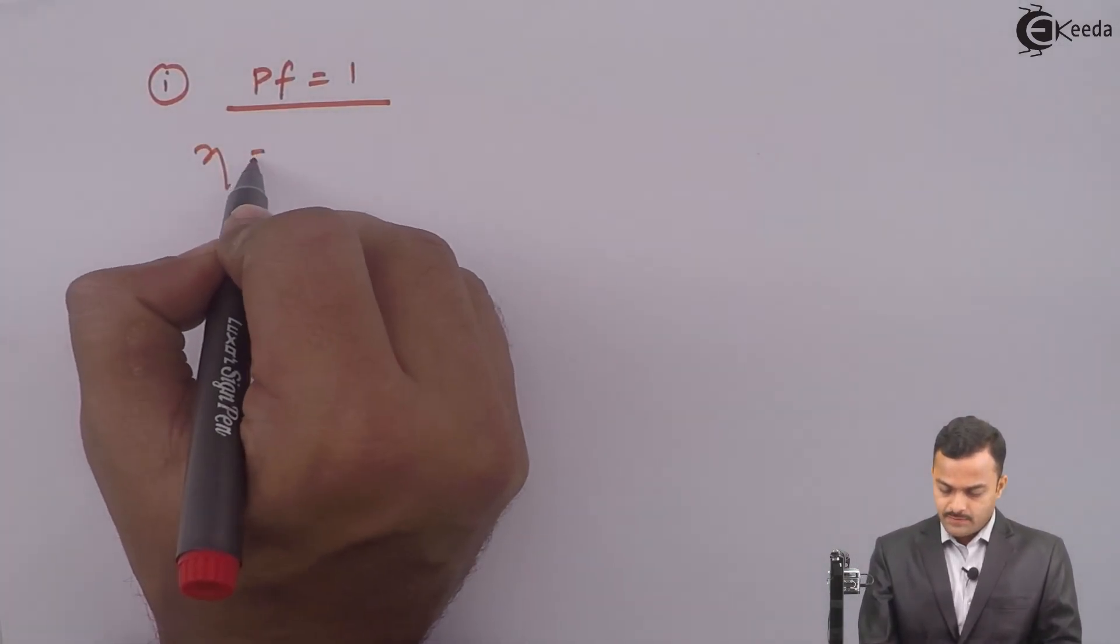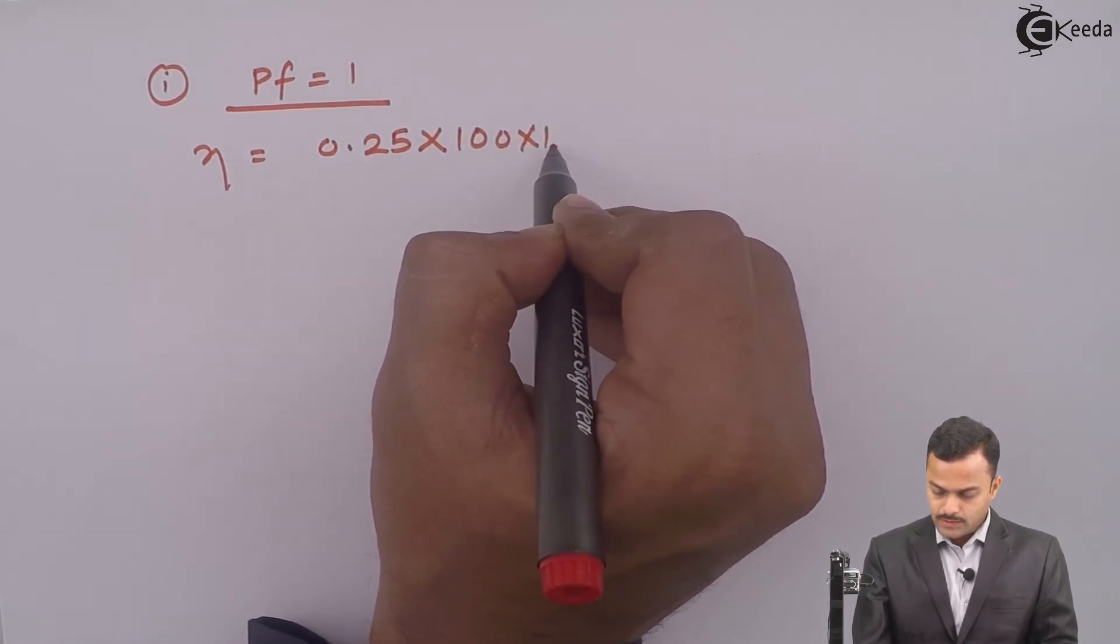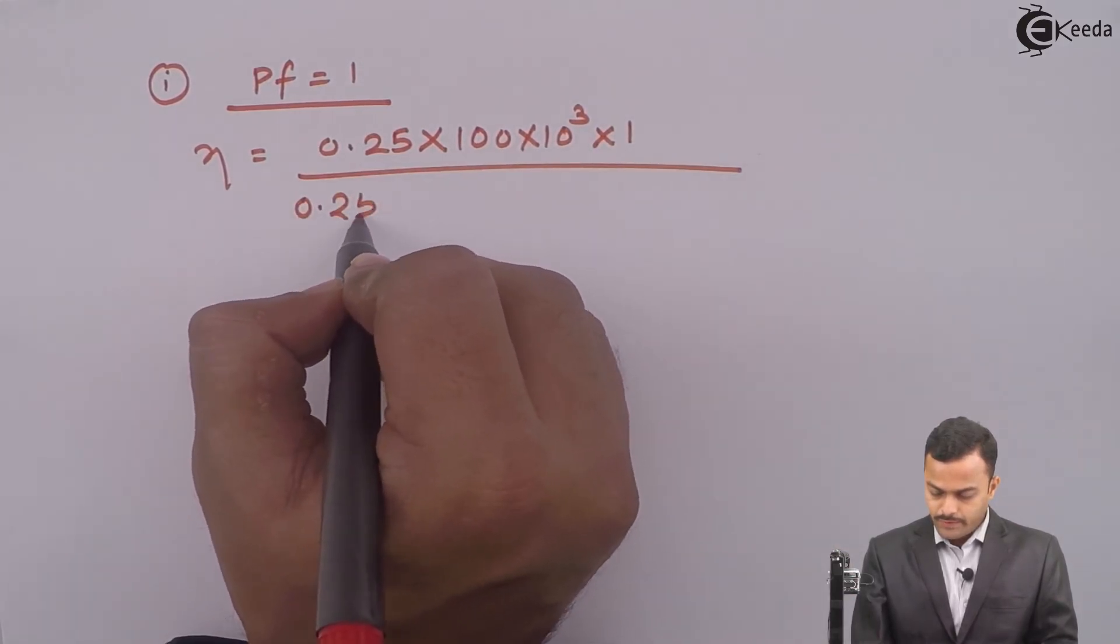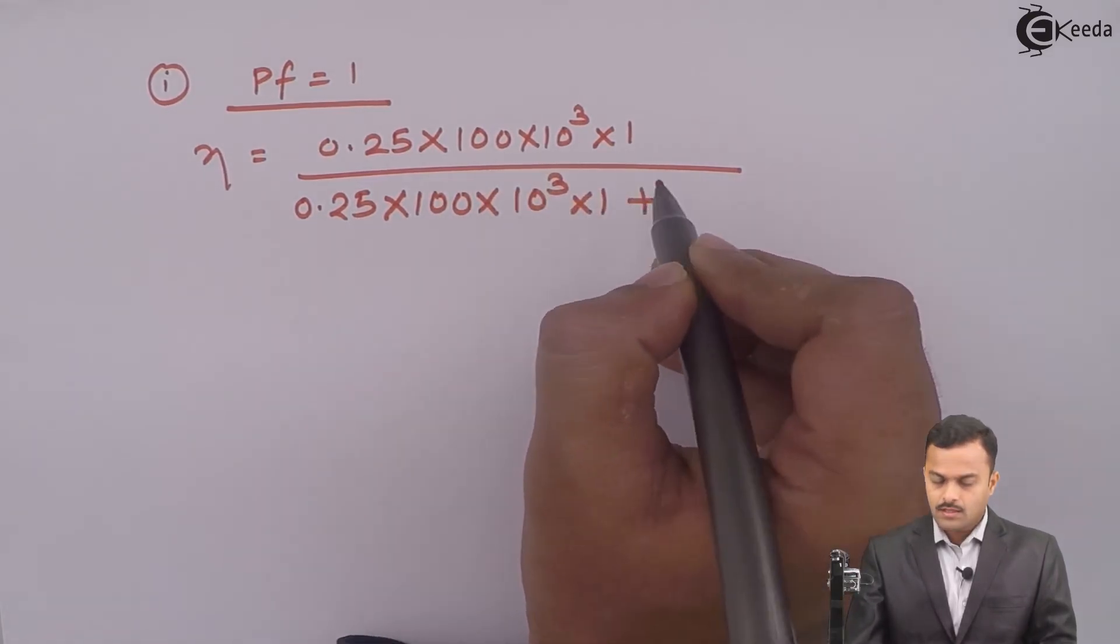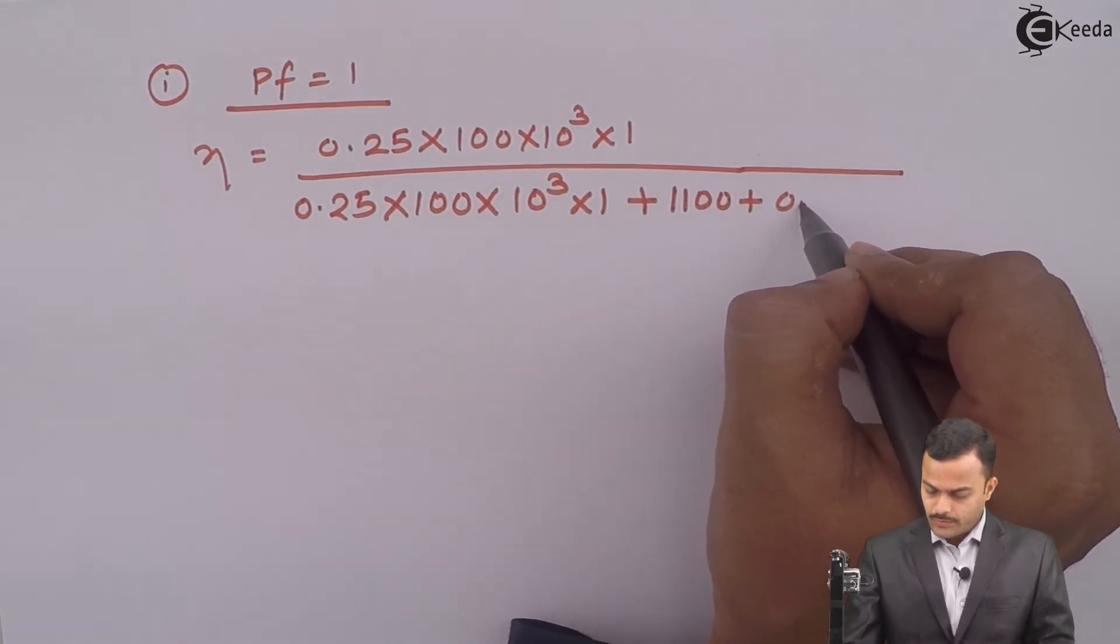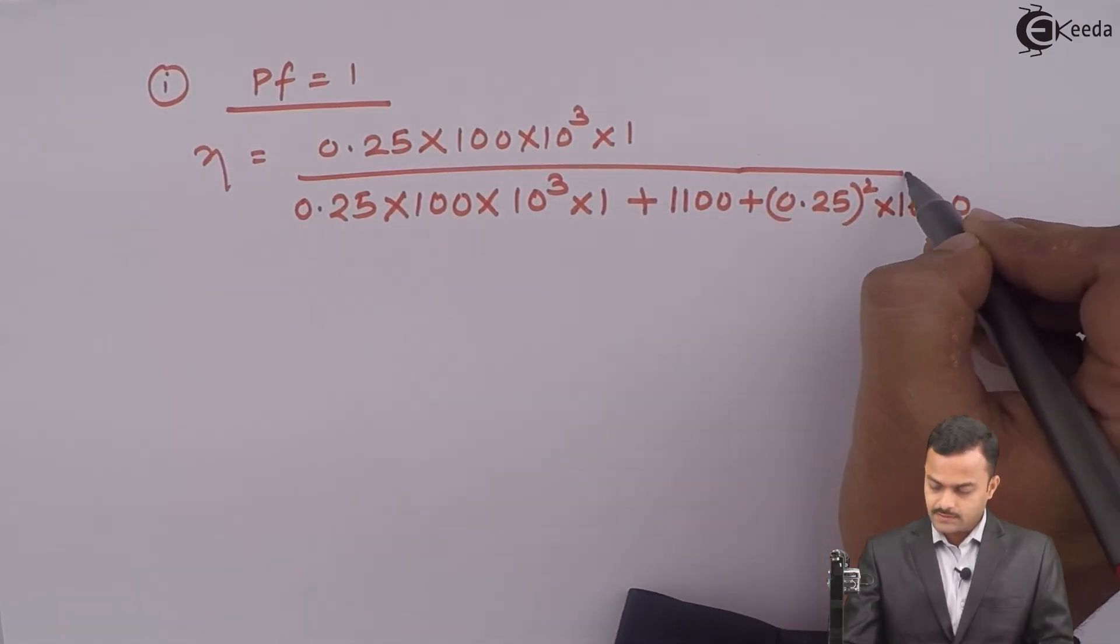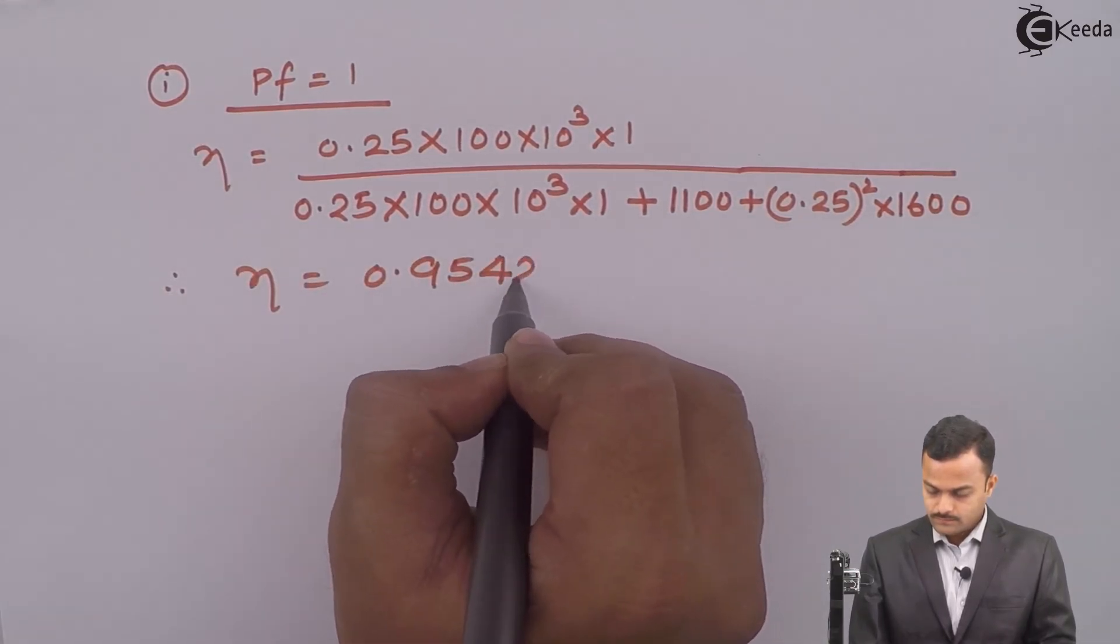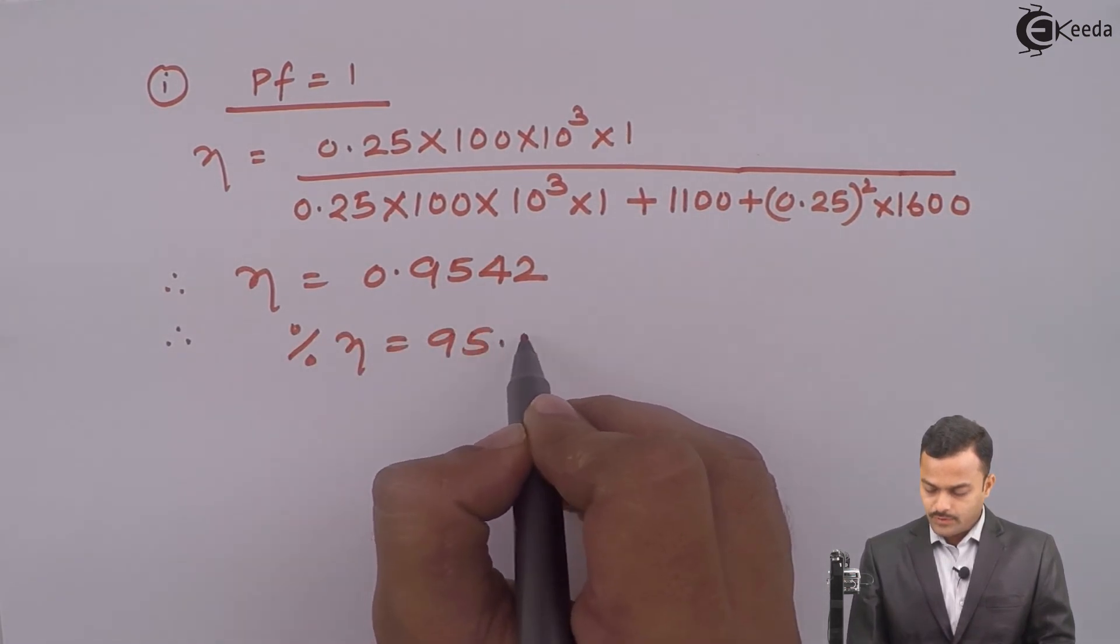So efficiency will be 0.25 multiplied by 100 into 10³ times power factor unity upon 0.25 multiplied by 100 into 10³ multiplied by 1 plus iron loss 1,100 plus 0.25² into WCUFL 1,600. So if you solve, you will get efficiency equal to 0.9542. In percentage, it is 95.42%.